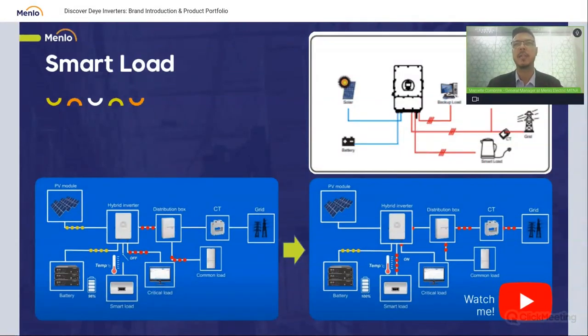Here we've got smart load. That same port can be used for smart load, or as we call it in other countries, essential loads. If there's a specific load that you want to give power to, you can connect that to the generator output side. That would be anything, for example an AC or a machine that doesn't need to switch off or that needs power constantly. Normally you've got an essential DB where you've got your very essential loads: security cameras, servers, computers, charging points. Don't forget the cell phone charging points, and then your fridges can also work.